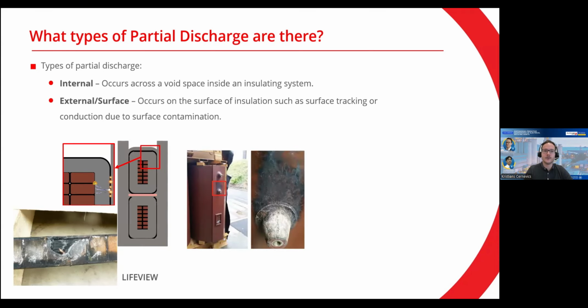The second type of discharge is the external surface discharge. This happens on the surface of the insulation, such as surface tracking, and usually happens due to surface contamination. So external or surface type discharges can actually be corrected a bit more easily. They can be spotted more easily because you can really see the damage that it's done. It's on the outside of the machine or on the side of some part of the machine. And this can be remedied by a thorough cleaning process. So by cleaning the machine and keeping up the maintenance of the machine, this can be in some way remedied.